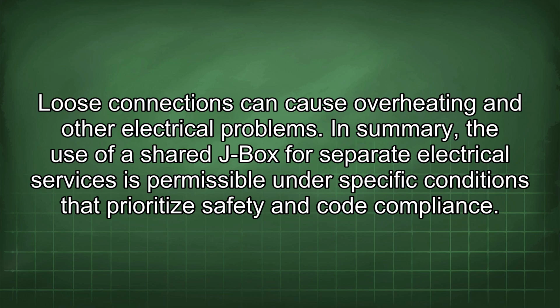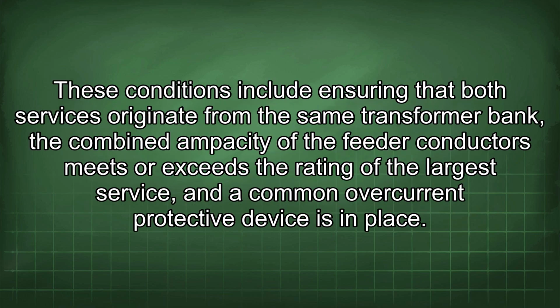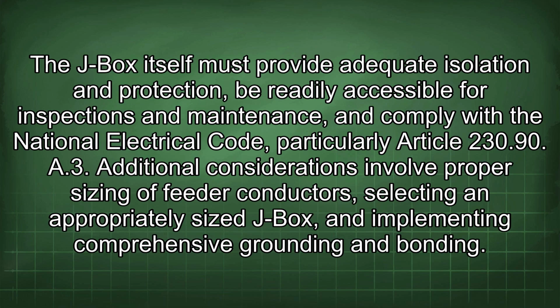In summary, the use of a shared J-box for separate electrical services is permissible under specific conditions that prioritize safety and code compliance. These conditions include ensuring that both services originate from the same transformer bank, the combined ampacity of the feeder conductors meets or exceeds the rating of the largest service, and a common overcurrent protective device is in place. The J-box itself must provide adequate isolation and protection, be readily accessible for inspections and maintenance, and comply with the National Electrical Code, particularly Article 230.90.